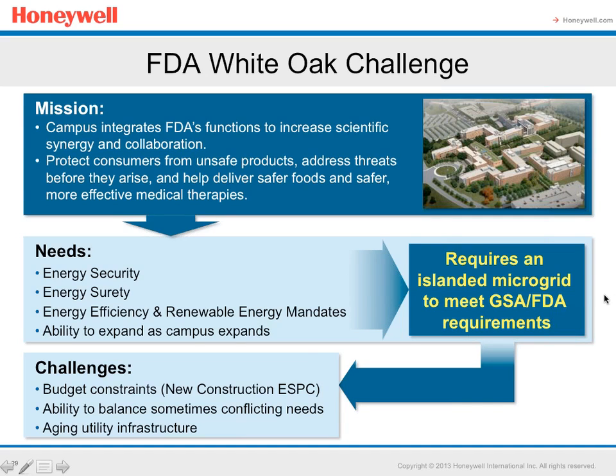The microgrid monitors continually the grid function and also monitors the weather. If they see a storm front coming, they'll switch to island mode manually. Every two cycles of our 60-cycle power system, they're sampling the grid. If the grid looks unstable, the campus goes into island mode automatically with no human intervention. They're always, always looking.